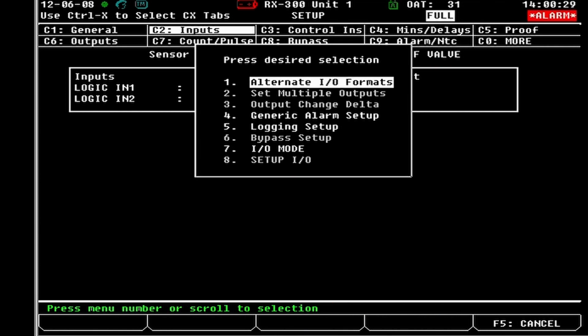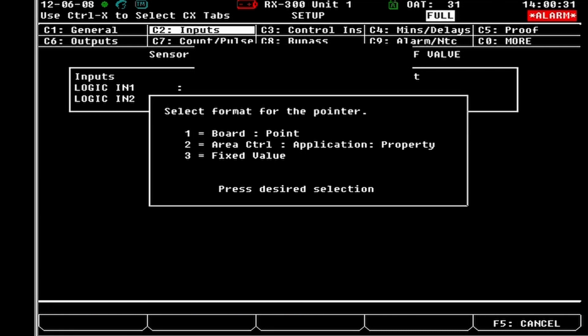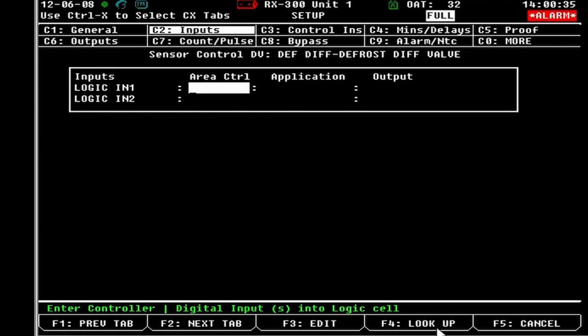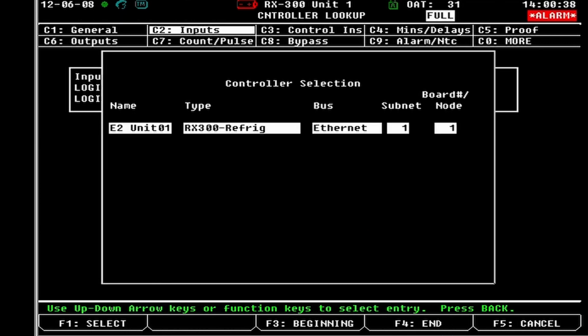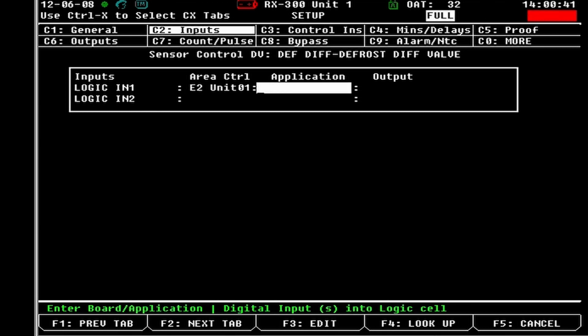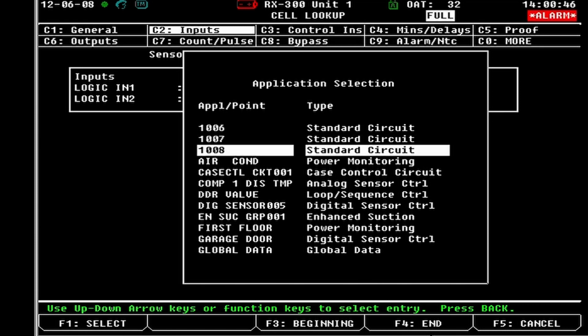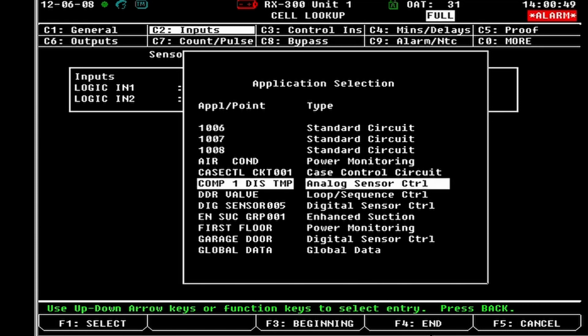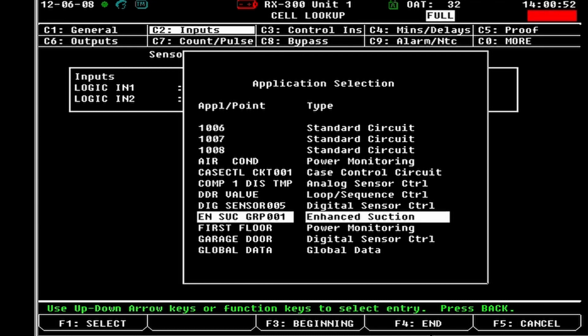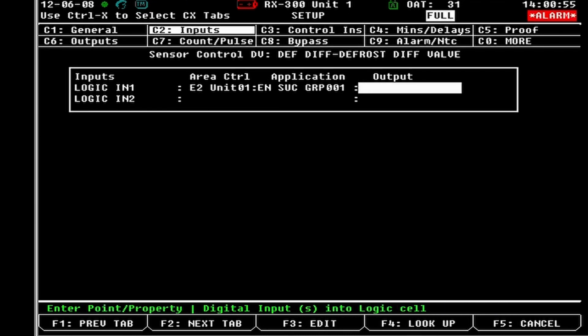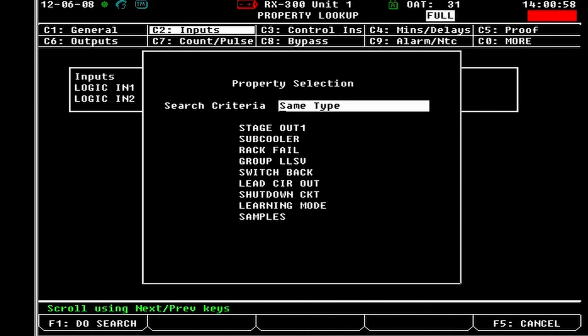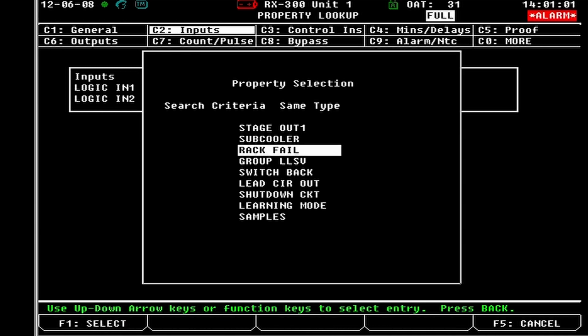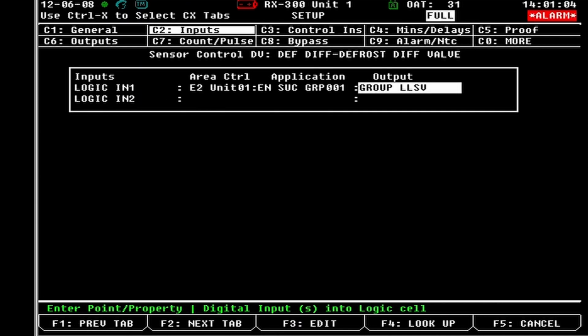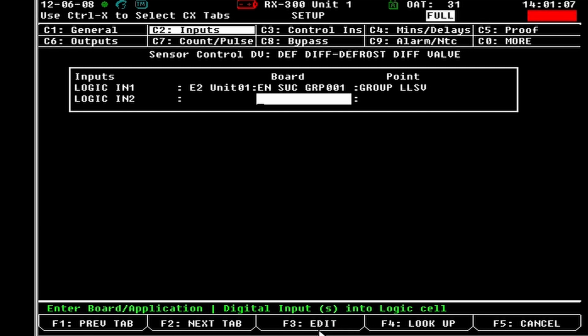We're going to go to alternative IO formats, and we're going to go to area control, since we're going to be taking these inputs from an actual control. So we're going to choose the condenser. We're choosing this E2. We're going to choose the enhanced suction. And we are going to choose group liquid-line solenoid. And then we're going to go down to this one. Same thing. See, it went back to board and point. This top one is area control.